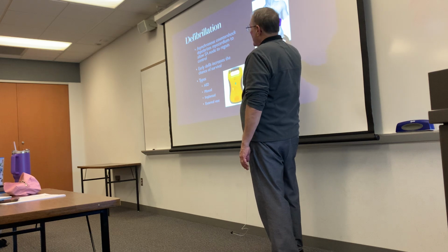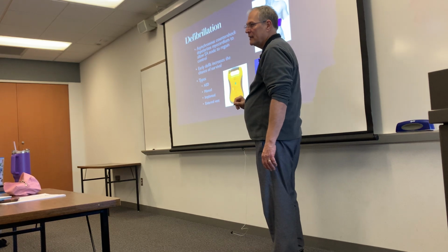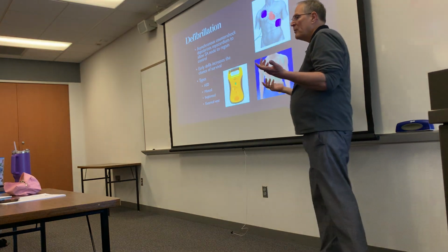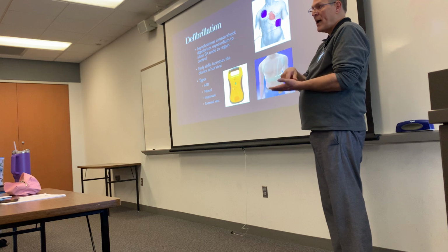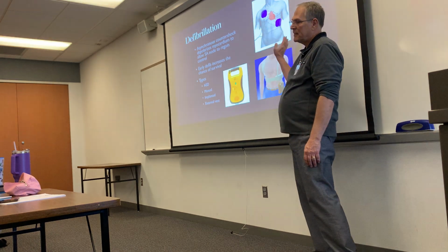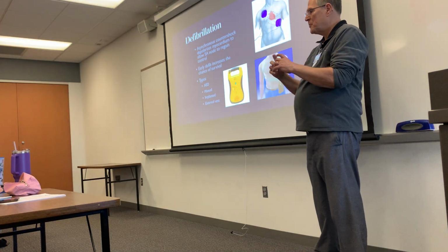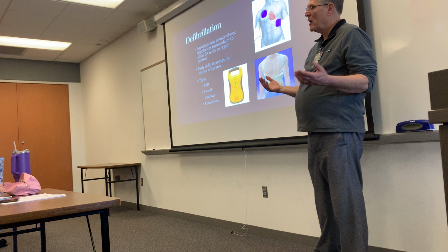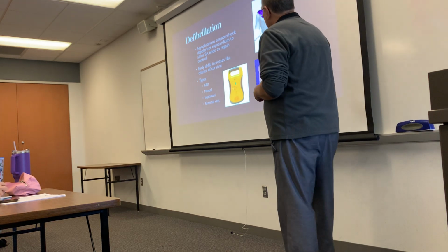When they first came out, they were monophasic, which meant it was dependent on how you put the pads on. These days, if you open up a defibrillator, you'll see there's a drawing right on the package, there's a drawing on the pad. It shows you where to put them, but most of them are biphasic. Meaning, even if you screw it up, even with the PEDS pads, which are smaller, it's sending shocks in both directions, so you're okay.